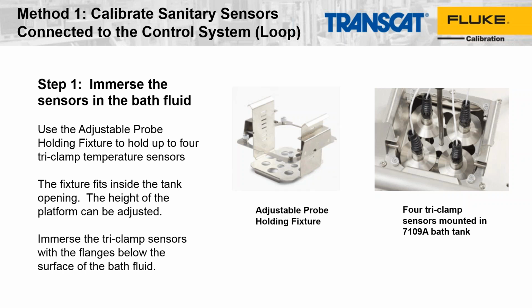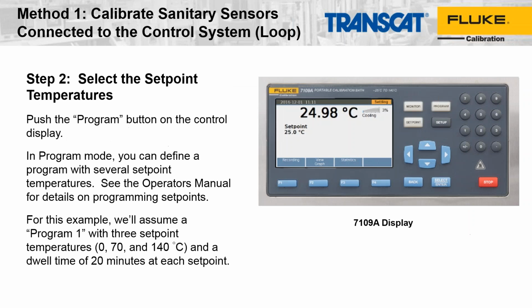Then step 2 is going into the 7109A display and set up a calibration program. And in the calibration program mode, you can program it to run through the temperature set points that you want to use, and have it do this automatically. And it also allows you to insert dwell time for each set point, so if you need some extra, you can specify the time you need to make sure you get the stability and uniformity that you need for your process.